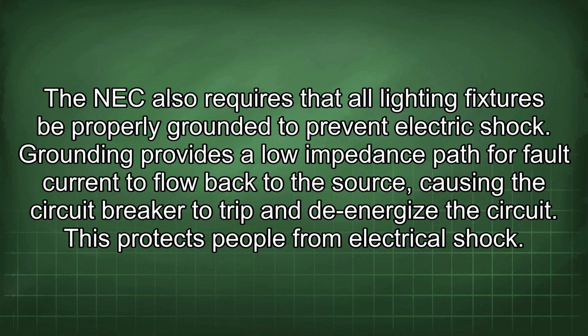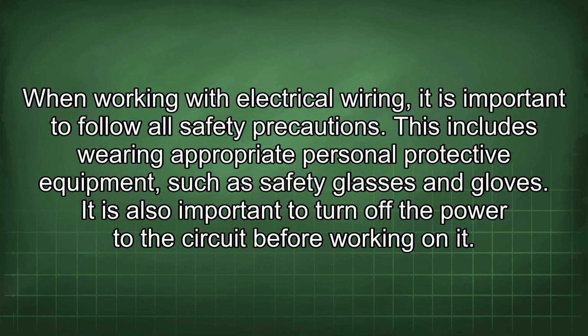Grounding provides a low impedance path for fault current to flow back to the source, causing the circuit breaker to trip and de-energize the circuit. This protects people from electrical shock. When working with electrical wiring, it is important to follow all safety precautions.